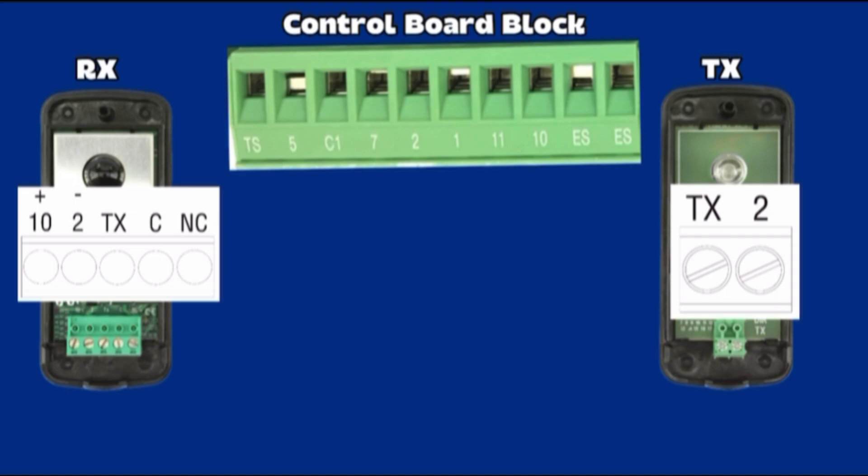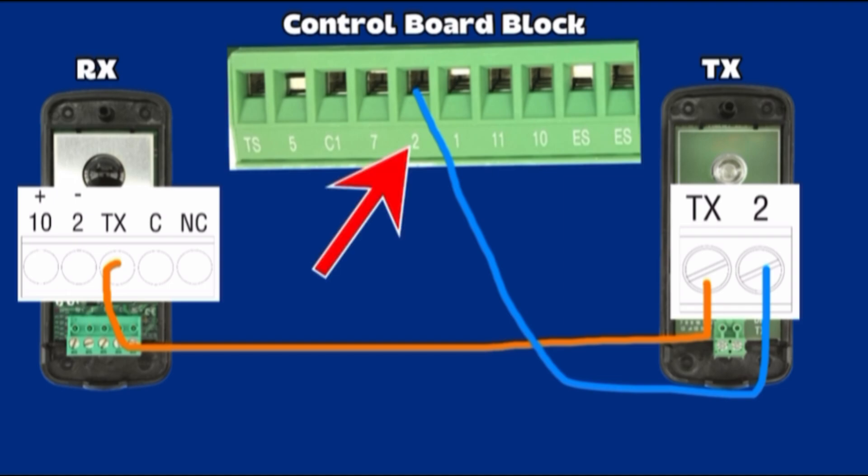Tx transmitter photo cell wiring. Tx terminal on transmitter connect to terminal Tx on receiver sensor. Terminal 2 of transmitter sensor connects on control board Terminal 2. Terminal 2 is ground and common. The transmitter only needs power, usually plus 24 volt DC from the control board.